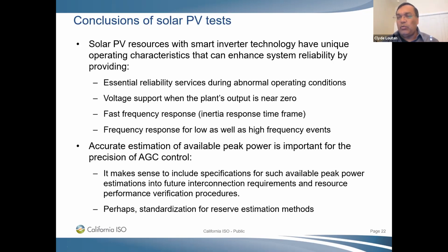Now they have certain requirements where they need to have low voltage ride-through capability and low frequency ride-through capability. If you have high frequency on the distribution, the new rooftop PV needs to back off production. But we already have roughly 12,000 megawatts without that capability. So we realized that the grid needed support from the distribution side, and those were some of the rules that were implemented.